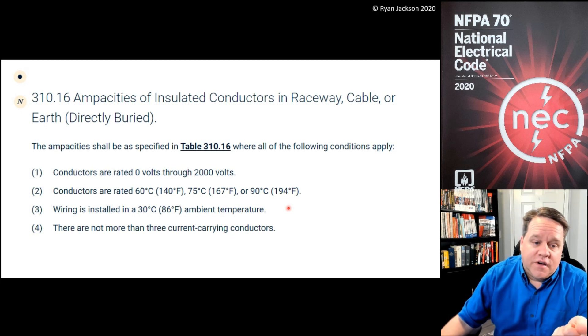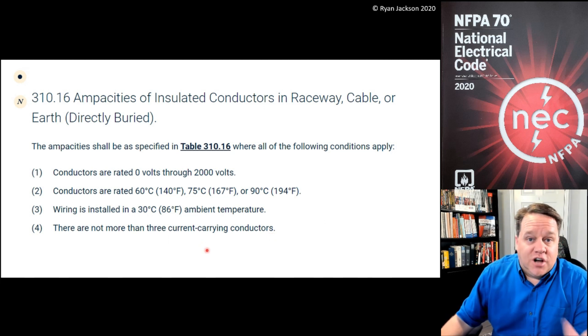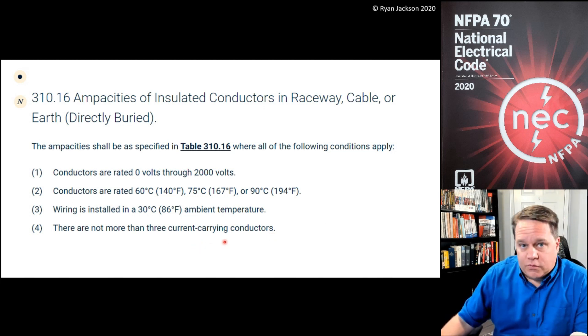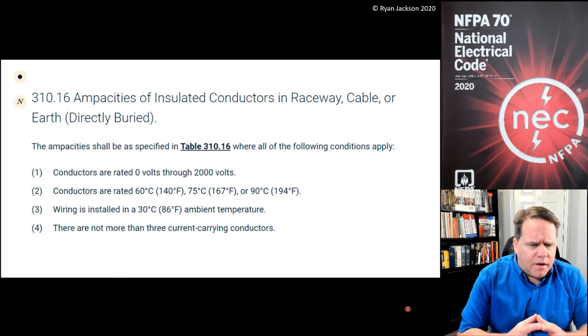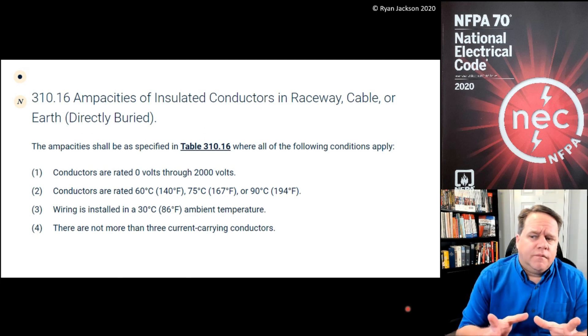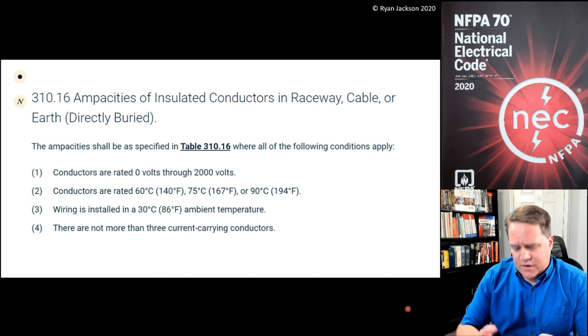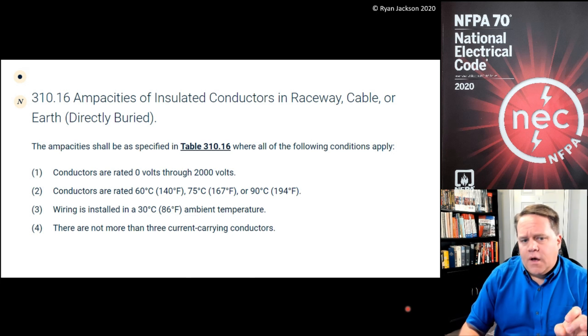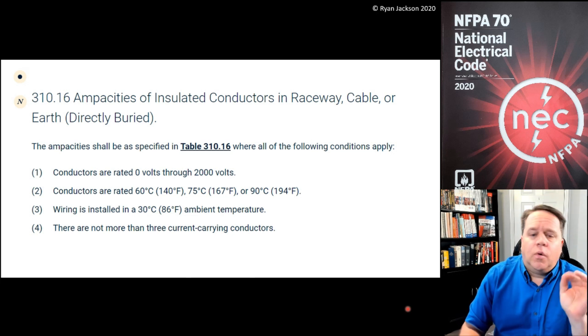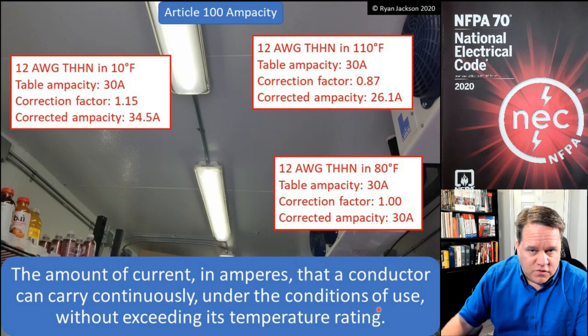So we have ambient temperature to concern ourselves with — if it's not 86°F, we have to apply a temperature correction factor. We also have the number of current-carrying conductors — if it's more than three, we have to apply an ampacity adjustment. I did a video earlier that covers what is and what is not a current-carrying conductor, because it's not as simple as saying every wire that's not green is a current-carrying conductor. But if I have more than three current-carrying conductors or I'm in an ambient temperature that's not 86°F, I've changed the conditions of use and I have to adjust the ampacity.